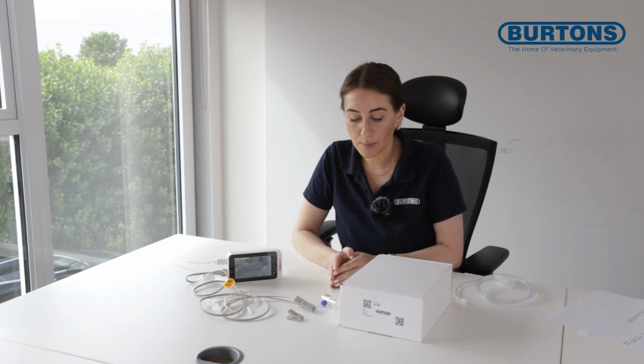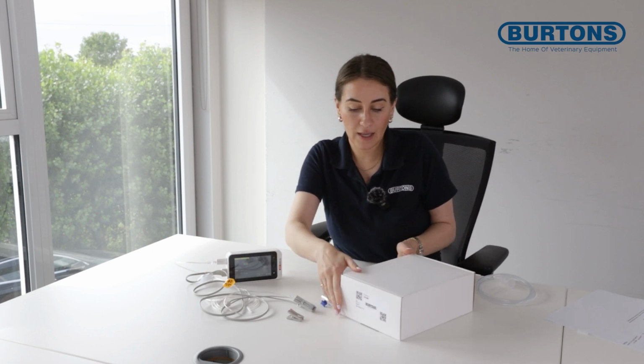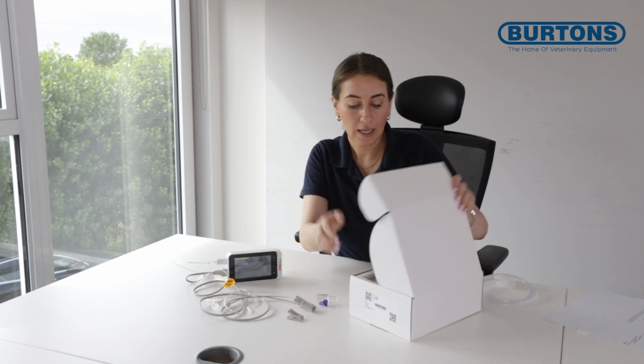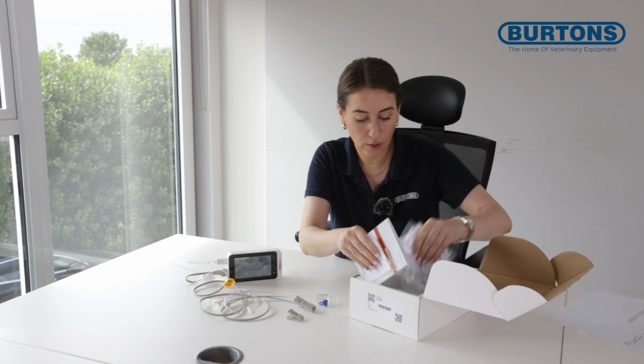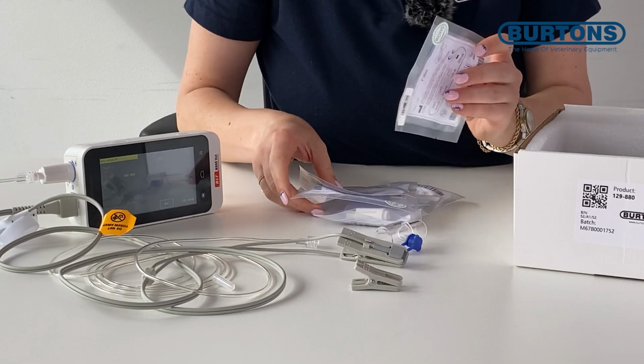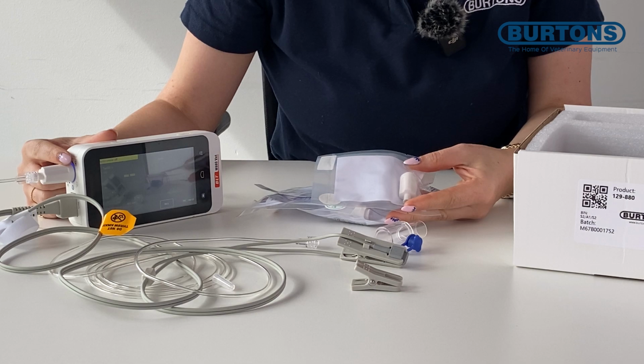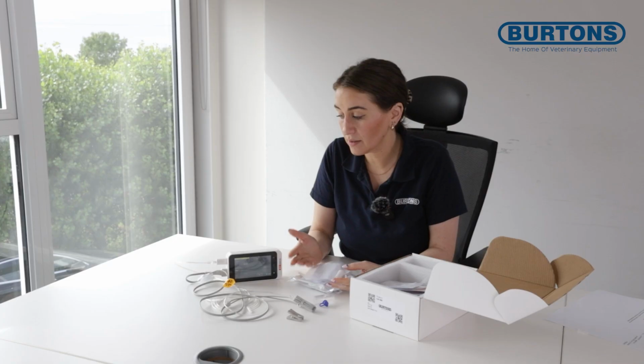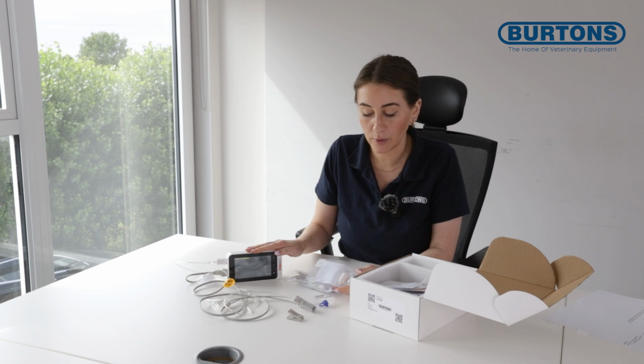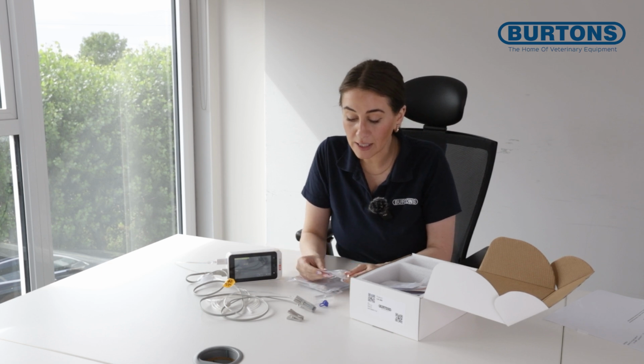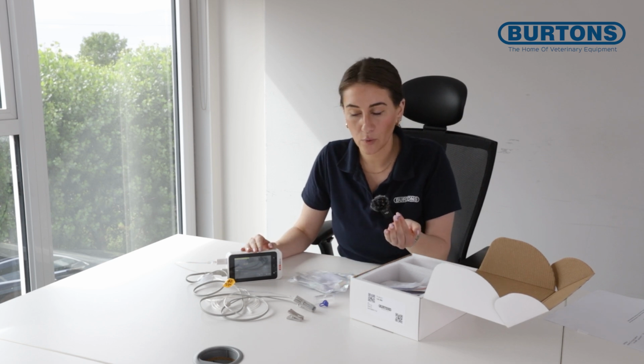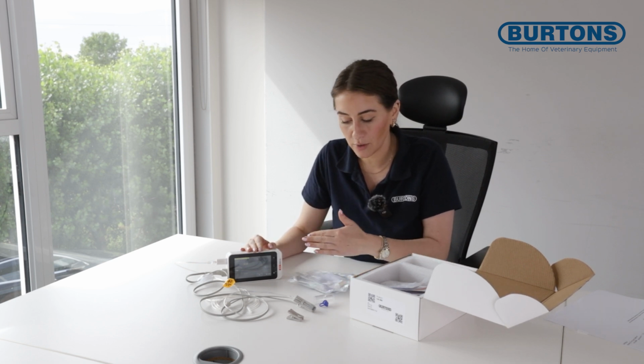So in terms of maintenance, cleaning and consumables, as part of the initial order included is a few of these filters. So we can see them here, and we have one attached to the machine already. The aim of this filter is to prevent water vapor from getting to the machine, which can damage the internal module inside. It's really subjective as to when these get changed, because a practice using this can have 600 surgeries in 1 month and another practice can have 200 surgeries.